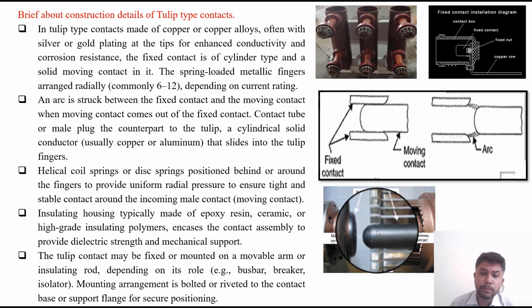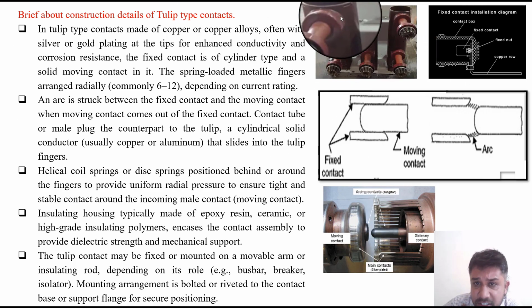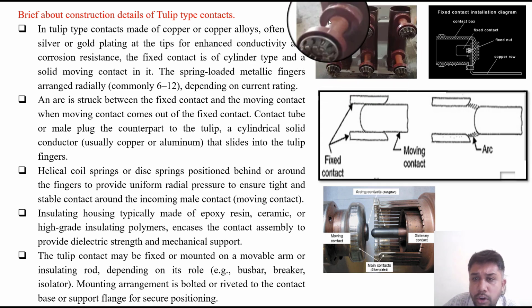Insulating housing, typically made of epoxy resin, ceramic or high-grade insulating polymers, encases the contact assembly to provide electrical dielectric strength and mechanical support. The tulip contact may be fixed or mounted on a movable arm or insulating rod, depending on its role, that is, either a busbar, breaker or isolator. The mounting arrangement is bolted or riveted to the contact base or support flange for secure positioning. So in the figure you can visualize this. This is the physical construction of a tulip type contact of a circuit breaker.